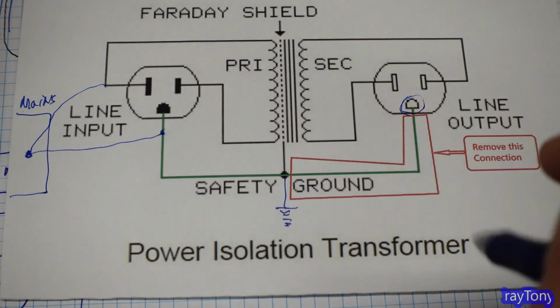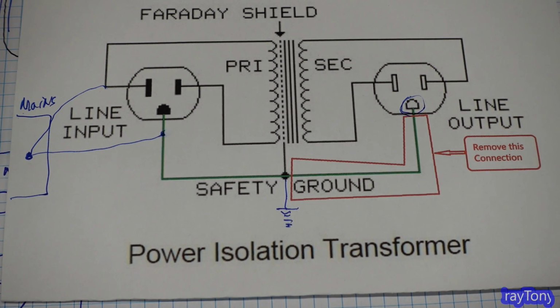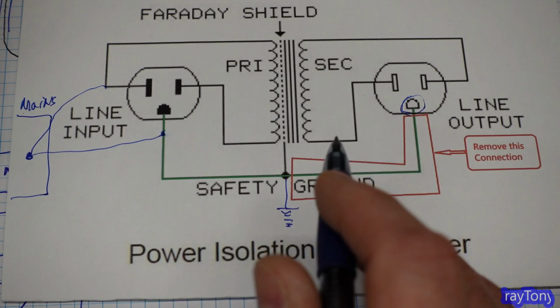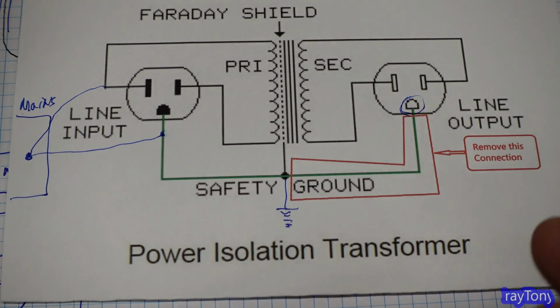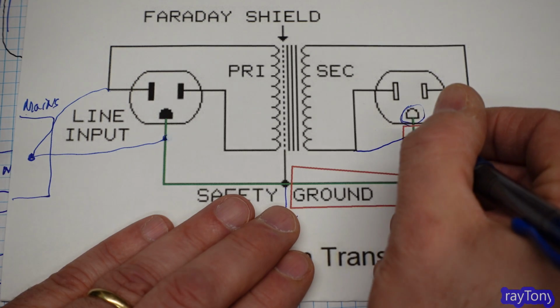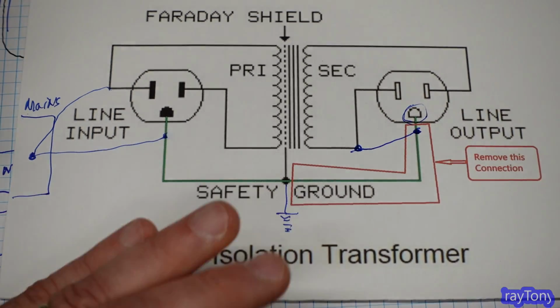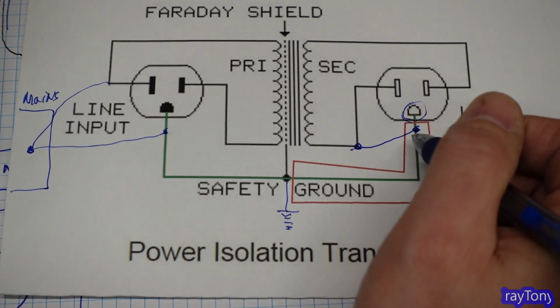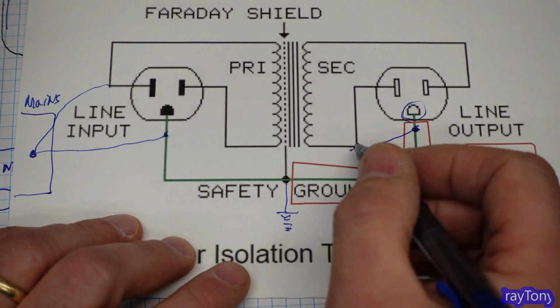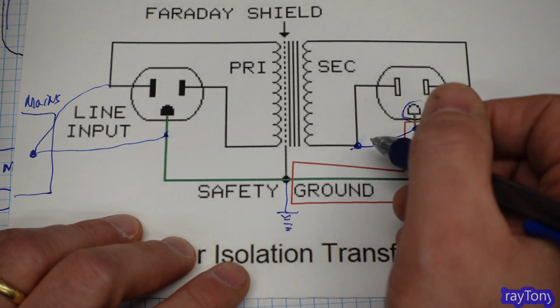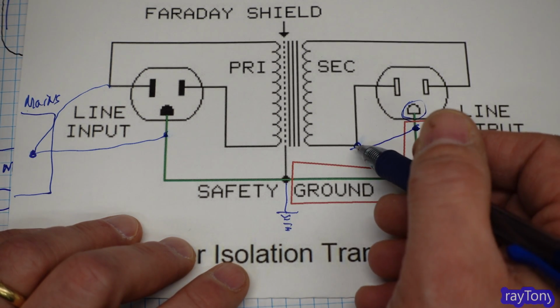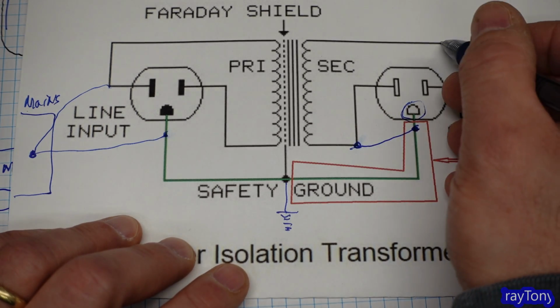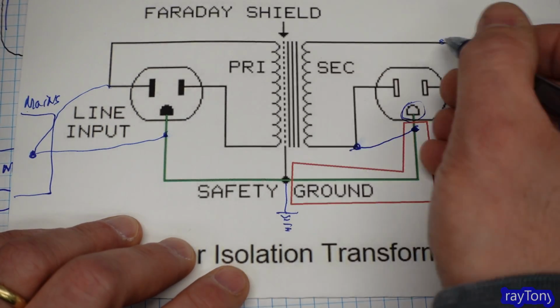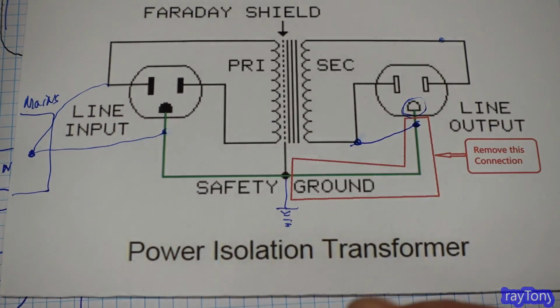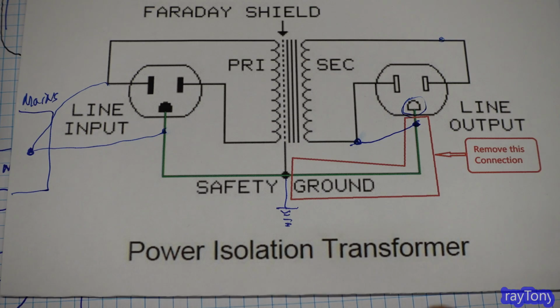That ensures you truly have an isolated secondary. With a 2-prong plug, this doesn't mean anything. Some isolation transformers, depending on design, will even have another bonding wire here—I've seen it, not all of them do. Those are really bad, because you've just introduced the neutral line to here. So if you touch your ground probe to something connected to this side, you've just introduced 120 volts across that ground lead, and you will cause a short. That's pretty uncommon, but it can happen.